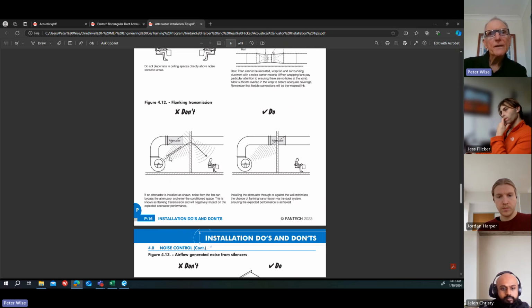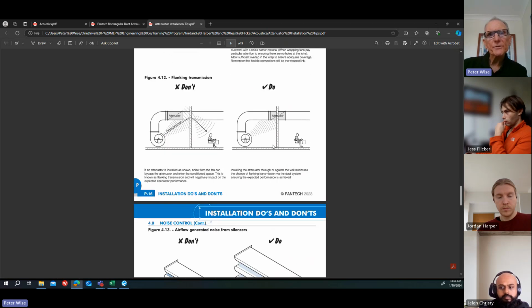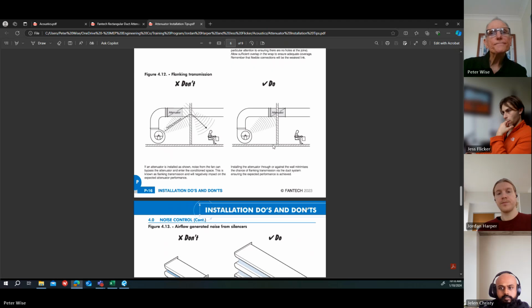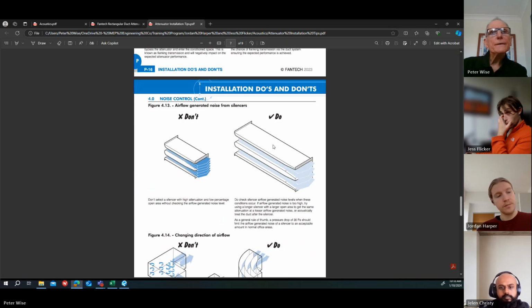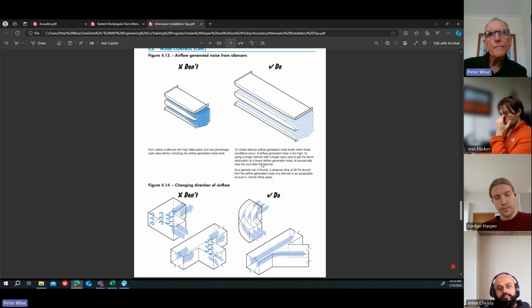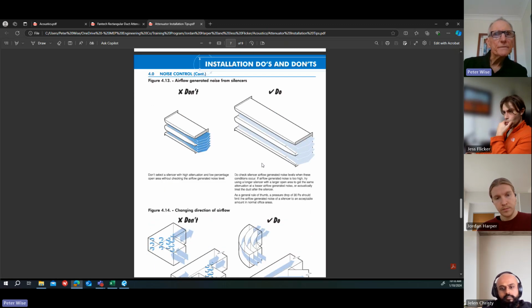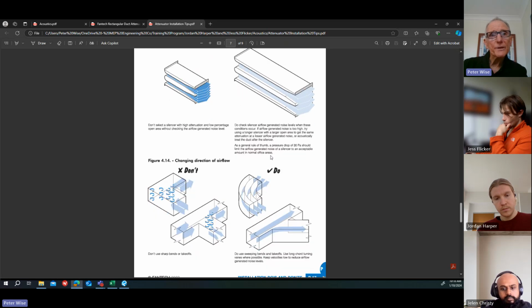They call it flanking transmission. The radiated noise from the fan casing can break into the duct and then break out of the duct, or it can break straight through the wall. With the attenuator there, that just gives you a better sound seal for the plant room wall. This is just talking about passageways through attenuators, and velocities. So the lower the velocity through the attenuator passageways, the less breakout you're going to get. We talked about that.